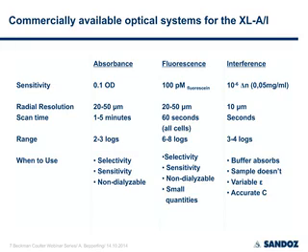Fluorescence optics is very useful for low concentrations and also for analysis of tight binding interactions, even in the subnanomolar range. But of course you have to label your protein, because currently the system is a solid-state laser with an excitation wavelength of 488 nanometers. And so you have to label your protein with a fluorescein-like dye, with the Atto or Alexa 488 series, for example, or attach an EGFP or EYFP moiety to the protein.